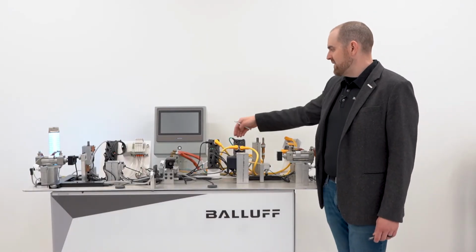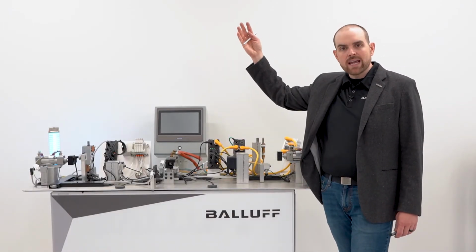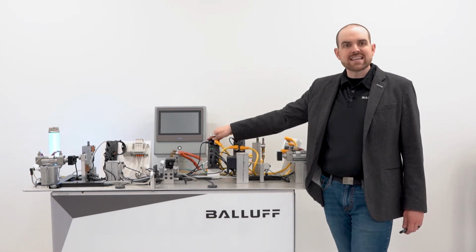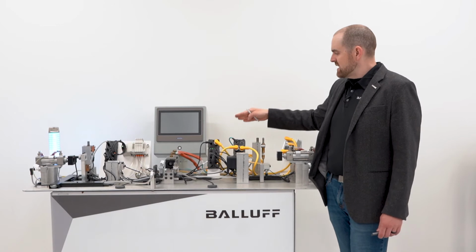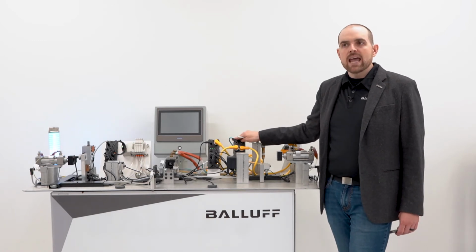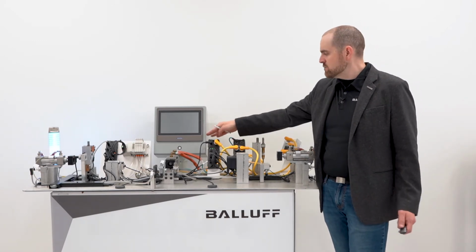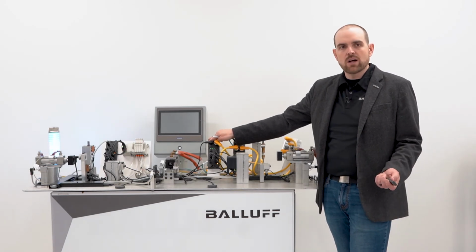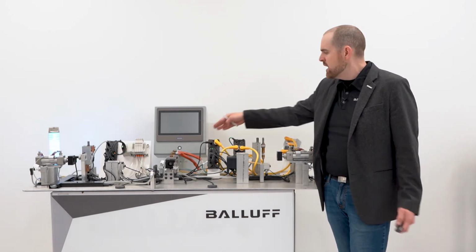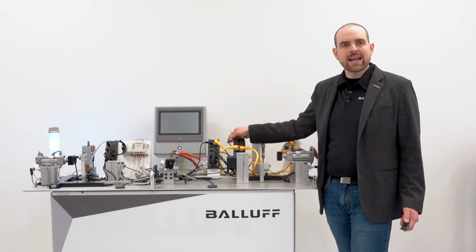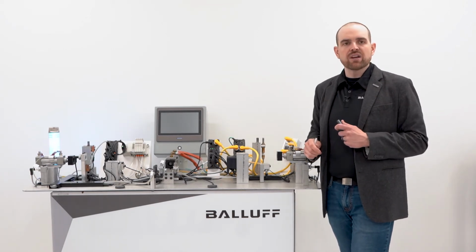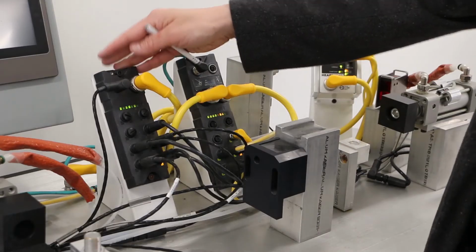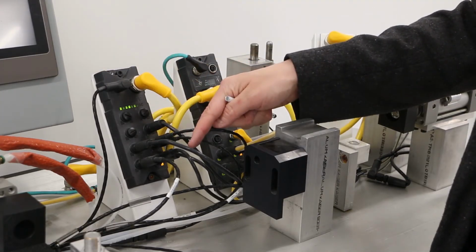But I like to say, let's get the network up out of harm's way, in a rafter or out of the welding environment. We send an I/O link device into the weld cell, and that allows the network to always stay communicating and allows for faster troubleshooting because we send the device into the hazardous area with the welding debris and the weld spatter, and we leave the master and the Ethernet connection outside of the welding environment, and we just send a cable to collect the I/O. So this is a really great solution for us.